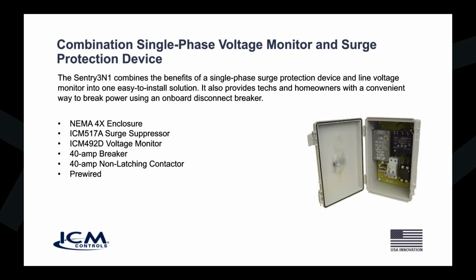So we've come up with a solution that covers the best of both worlds. You want the protection of that surge protection for all those fast acting transient surges caused by power grid changes, lightning in the upper atmosphere, downed power lines, bad transformers on the power pole, all those things that are creating surges. You've got to protect against that. But we also want to protect against those power grid level changes during peak periods when maybe the voltage goes from 240 up to 255, so we need to have both.